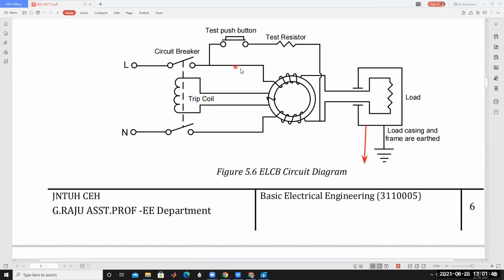Whatever current enters from here, some current flows through the device to the ground, to earth. So the current enters here, some amount of current passes to the ground, and the remaining current passes to the neutral. That means there is a difference between the line current and the neutral current. Under faulty conditions, they are not equal. For example, 5 amps is entering, and because of the earth leakage, some amount, say 2 amps, flows through the ground, and the remaining 3 amps returns in this direction.